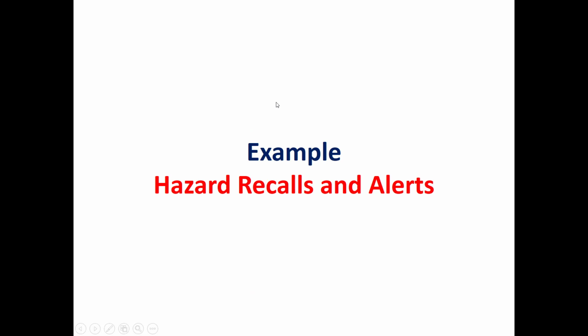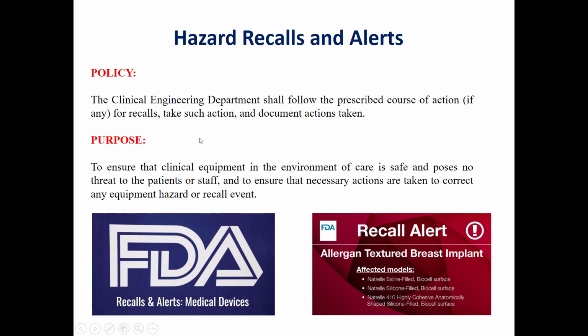Now we'll give an example about the hazard recalls and alerts in the clinical engineering department, the policy and the procedure about it, to clarify what is a policy and what is a procedure. So the policy of hazard recalls and alerts: the clinical engineering department shall follow the prescribed course of action for recalls, take such action, and document the actions taken.